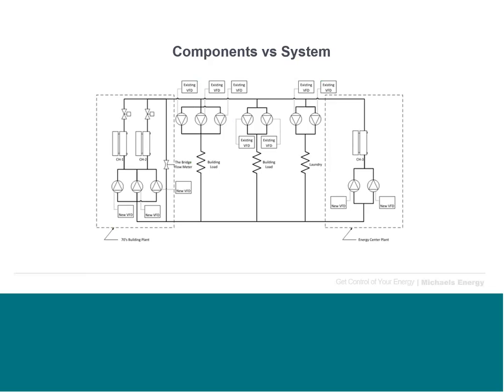Another thing we typically suggest is trying to have operators understand above a component level in their systems. Looking at the system level can give a better picture of how all the different pieces come together. But one thing I hear very frequently is that operators don't really understand how that system works as a cohesive whole. Oftentimes, like in this diagram on the screen, there may be separate plants - in this case, two different cooling plants on different sides of the building - and those cooling plants operate independently of each other.